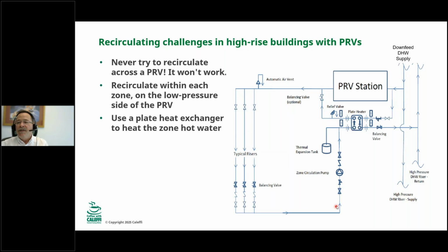I know this is expensive. Plate heat exchangers aren't cheap. You can see there's a lot of devices in here. You have air vents and thermal expansion tanks and balancing valves, but it is one way to do it on the downstream side of a PRV station. That would be expensive if you had to do that on every third or fourth floor, but it's a great solution. We know it's proven, and we know that it works.